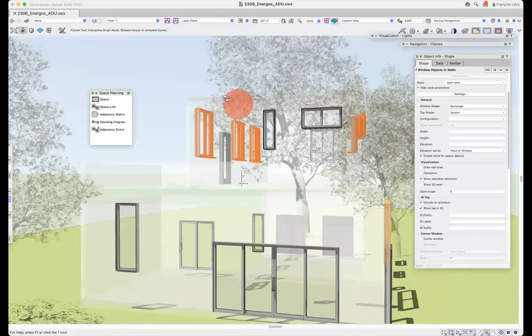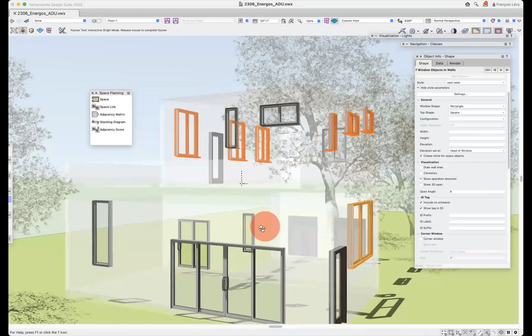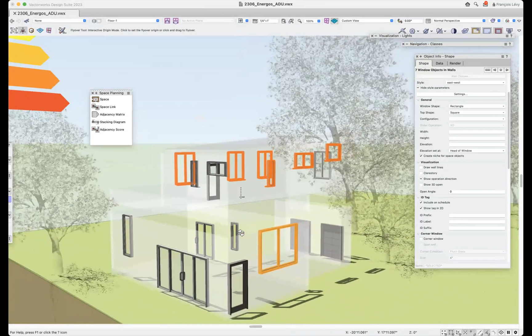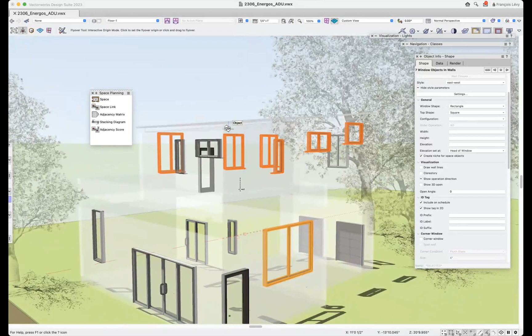Now the bad news is, I guess, that if I were to model a bunch of awnings or canopies over my south windows and south door to evaluate how that would affect building performance, it doesn't matter—I can model those shading devices, have Energos recalculate the performance, and nothing would change. Because again, this isn't really a finite element analysis; it's not running a year's worth of solar animations to evaluate how much of a specific window is shaded or exposed to direct solar insolation, as you'll see when we do the calculations—they're very quick.